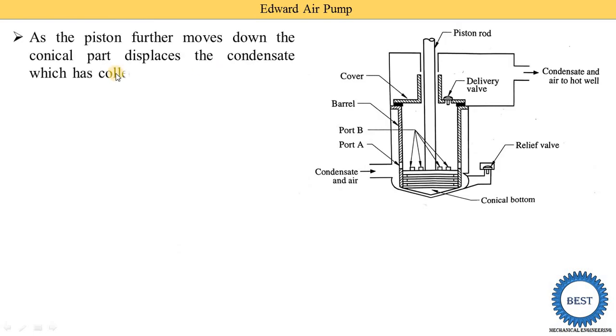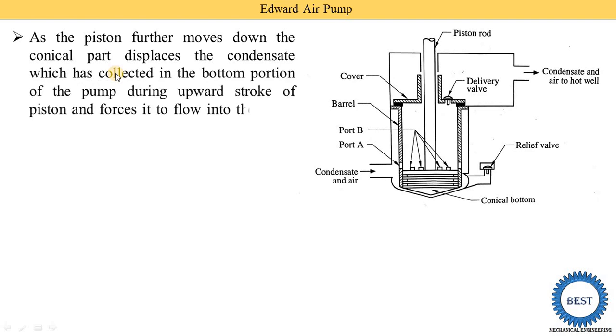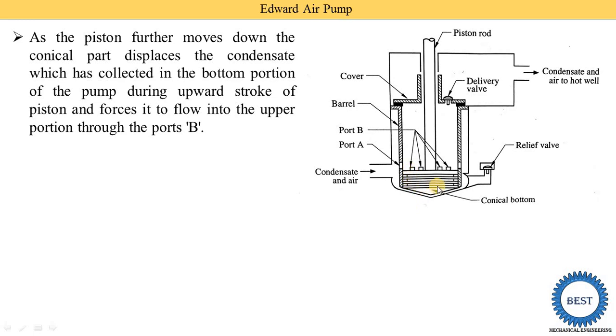As the piston moves further down, the conical part displaces the condensate which has collected in the bottom portion of the pump during the upward stroke of the piston, and forces it to flow into the upper portion through port B. So when the piston moves downward, the air and condensate below the piston move to the upper side of the piston through port B.